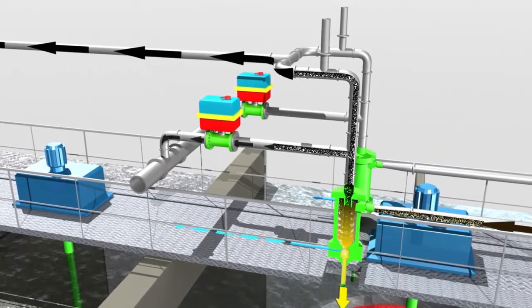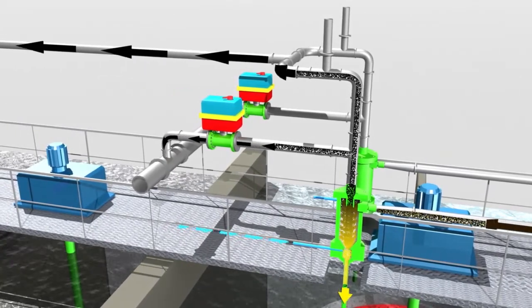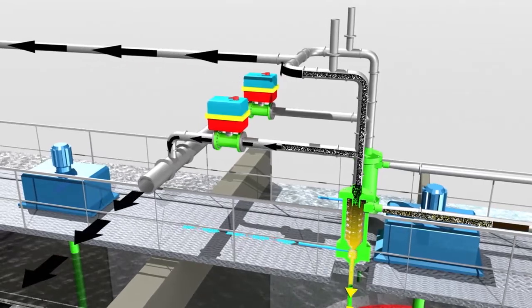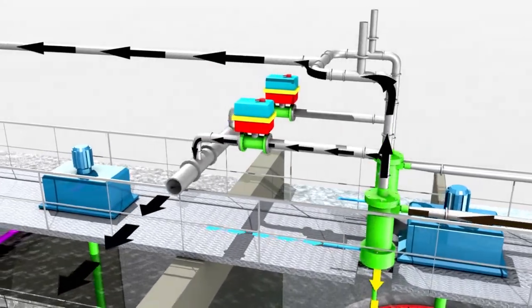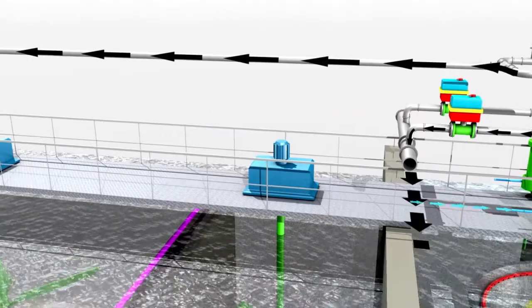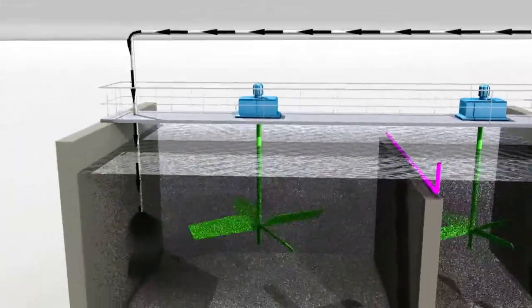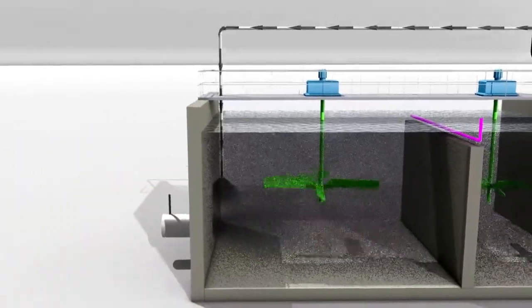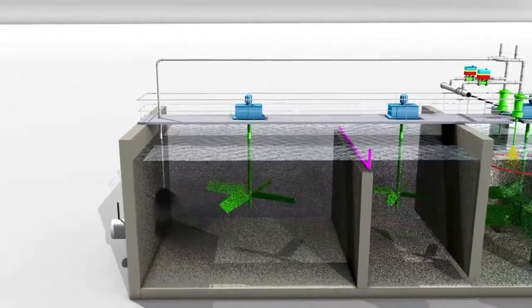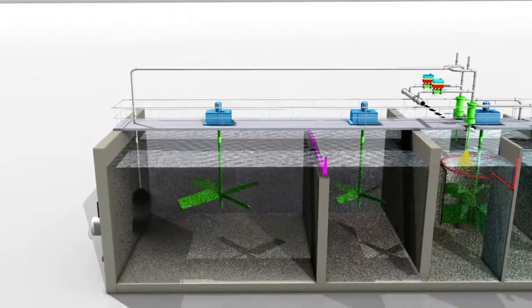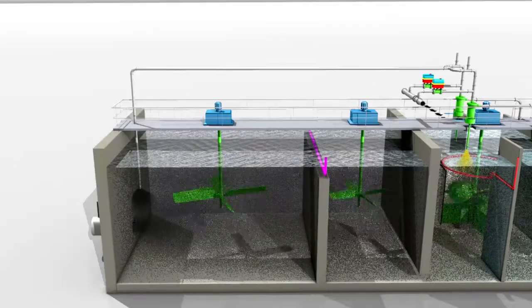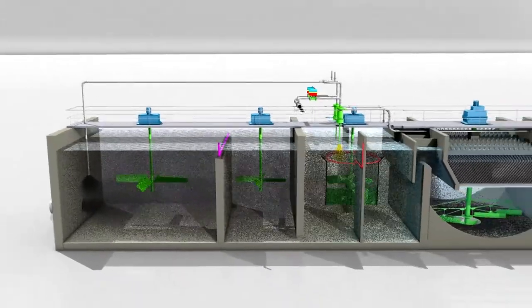With the aid of regulating valves, approximately 5% of the overflow is discharged to waste for system purge of the saturated activated carbon, whereas the remainder of the flow is recycled back to the contact tank for reuse of the non-saturated activated carbon. The discharge to waste is minimal, corresponding to water losses of about 0.3% of the influent flow.